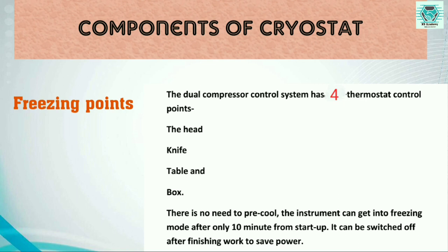The cryostat sections work using very low temperature, which saves energy and time and also reduces ice crystal condensation. The rapid freezing system can be switched off manually at any time. After working eight hours, the rapid freezing system will switch off automatically.